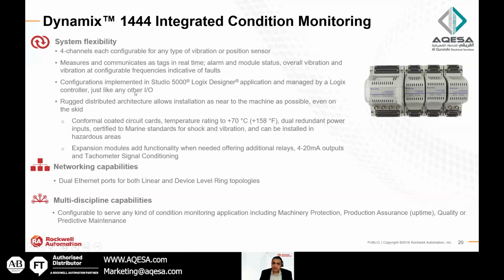Configuration is also implemented by Logix Designer, Studio 5000. The benefit of having all the information of vibration, the spectrum and the bands, frequencies, amplitudes, everything sent to the CPU is that on the CPU, with a small ladder, you can know the root cause of vibration. You don't only tell the operator that there is a high vibration alarm. You tell the operator that there is unbalance on your machine or misalignment or whatever.